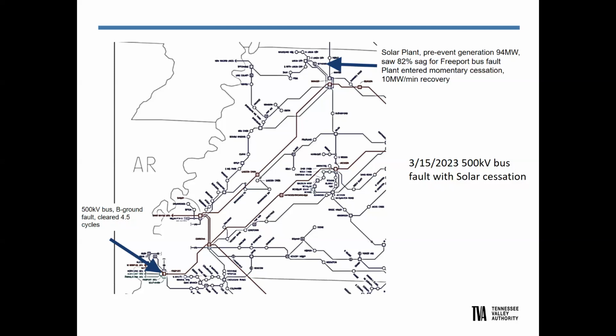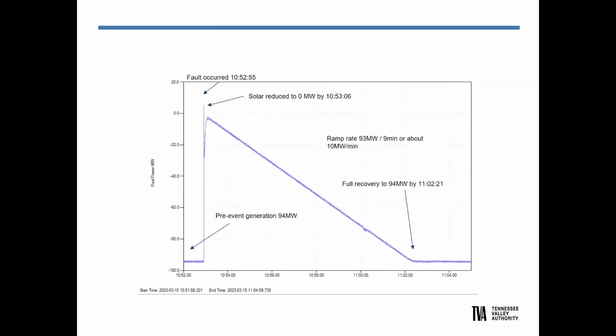The solar plant saw an 82% voltage sag for that bus fault. Pre-event, they were running about 100 megawatts, 94 megawatts. The plant entered momentary cessation, nearly dropped to zero with about a 10 megawatt per minute recovery. If you go to the next slide, you'll see here the megawatt output as you're looking from the meter into the plant, shows negative.